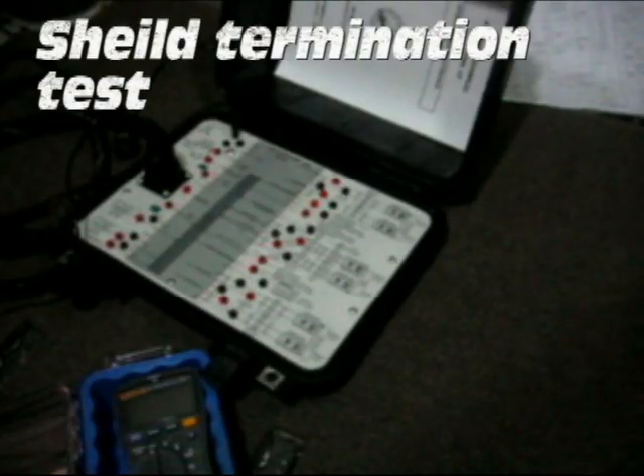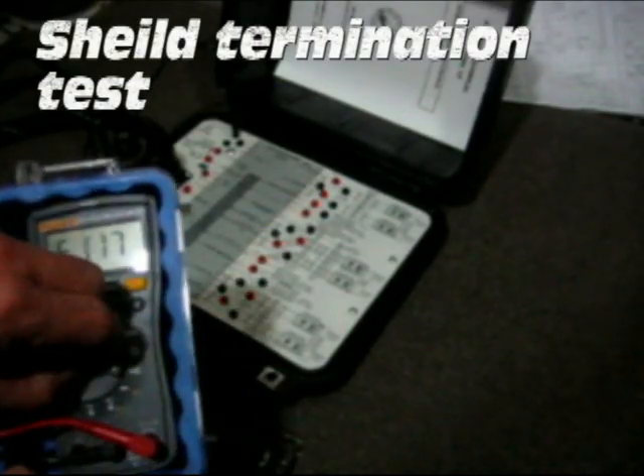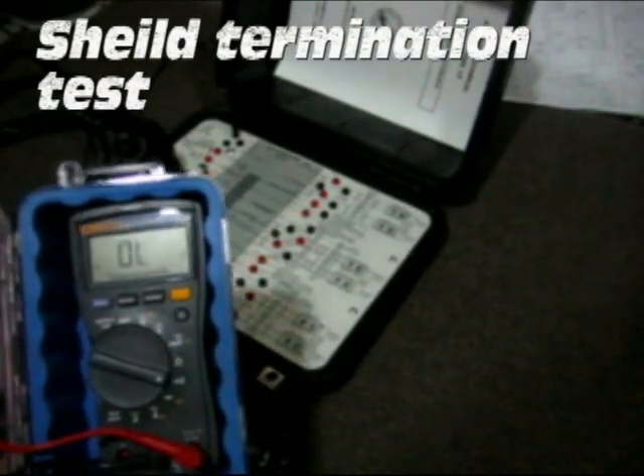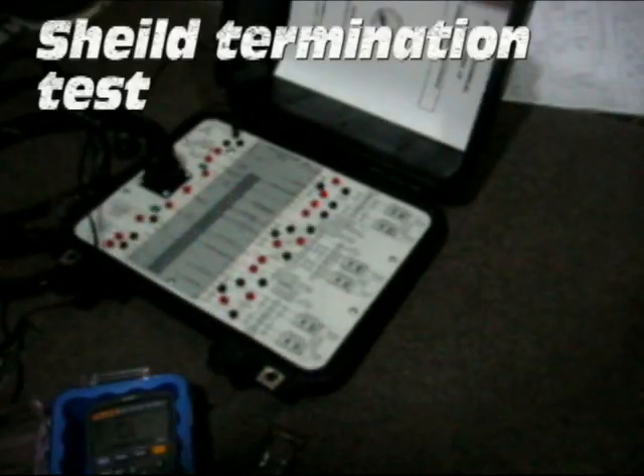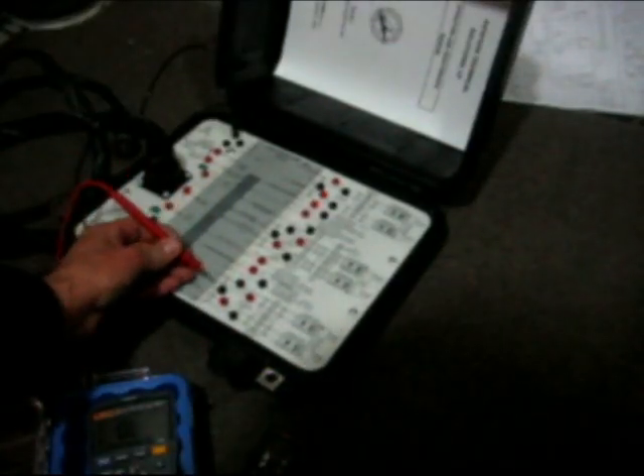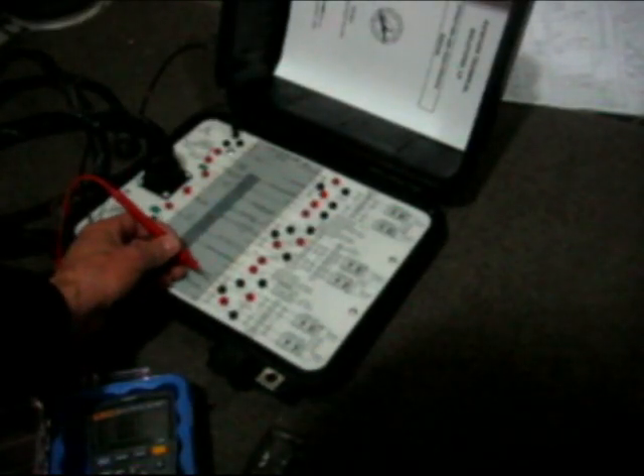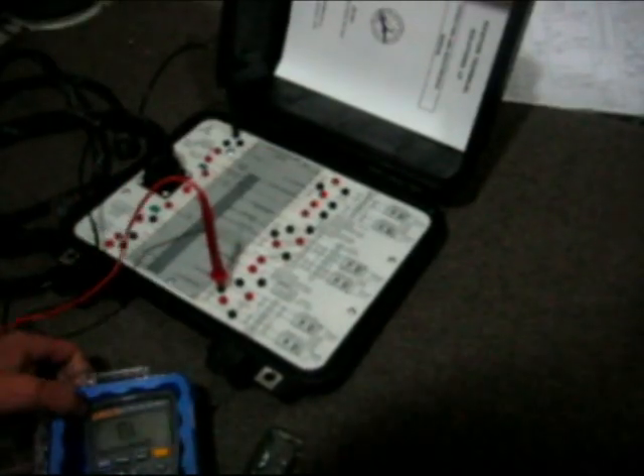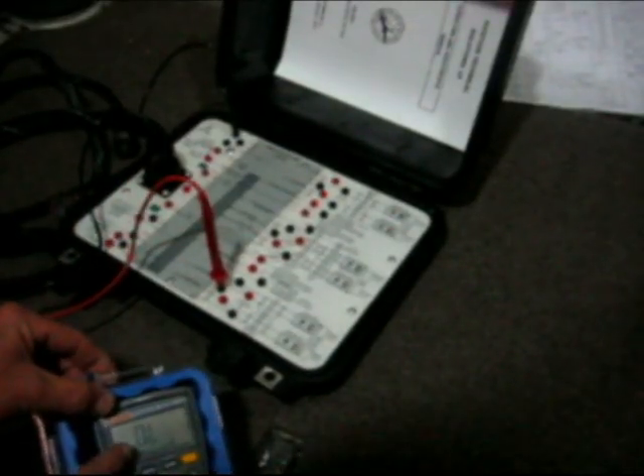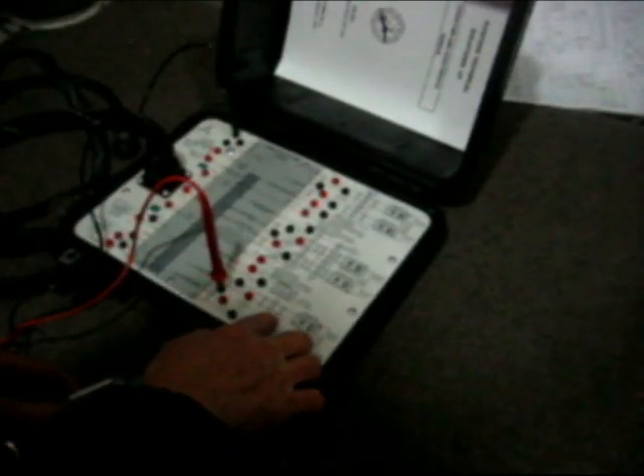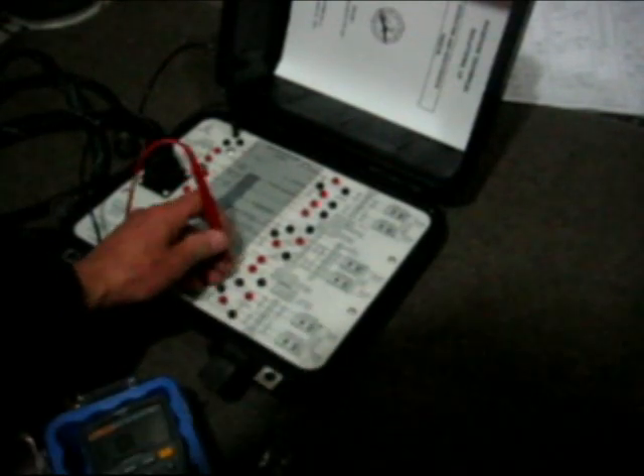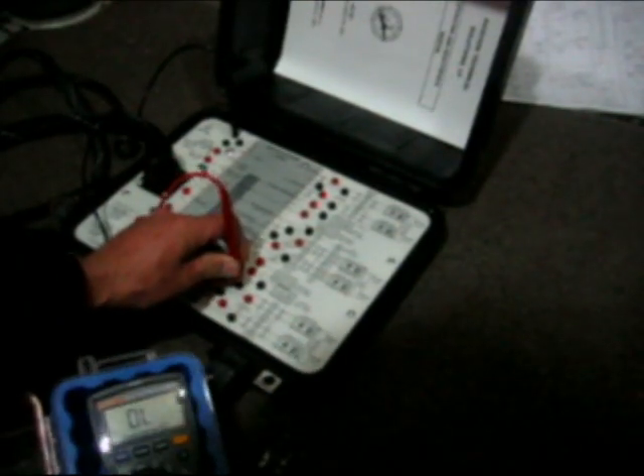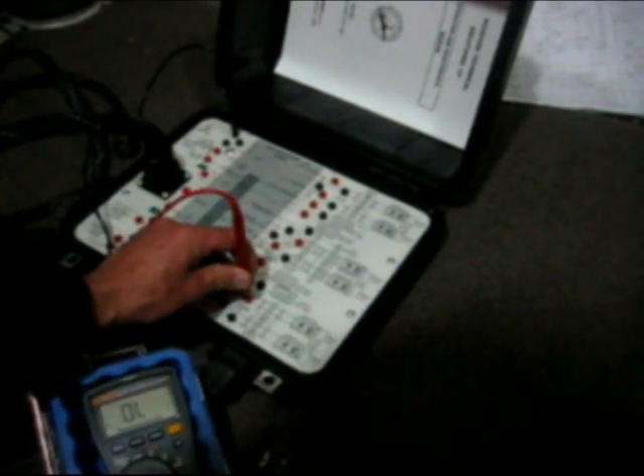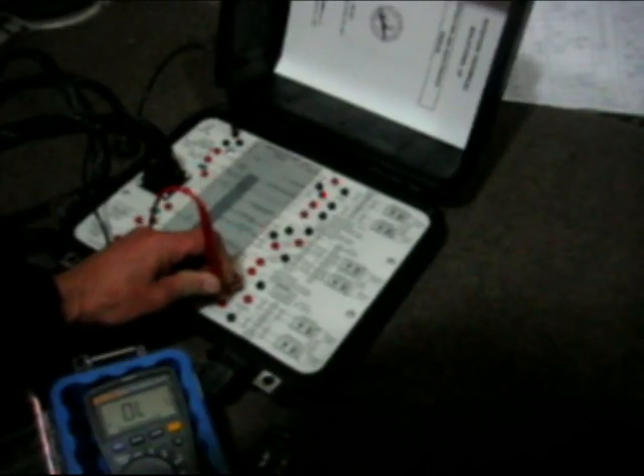This time we'll do a shielding test. We'll move our voltmeter to continuity. As drawn here, as long as the unit's not plugged in, the shielding just has to be open — it cannot go out here and touch these wires. The transducer wires must not go to ground.